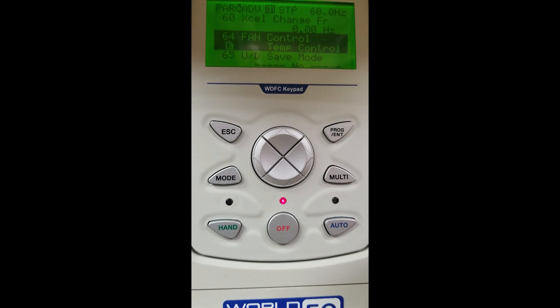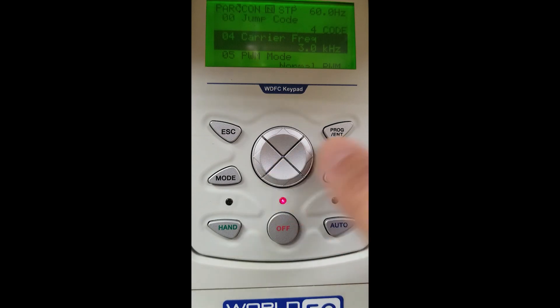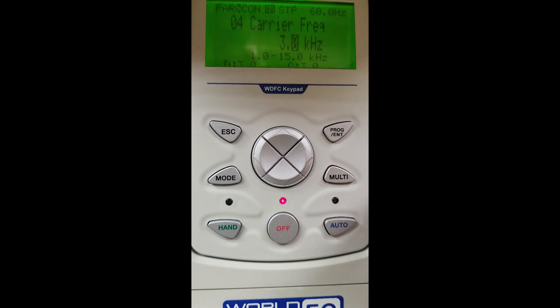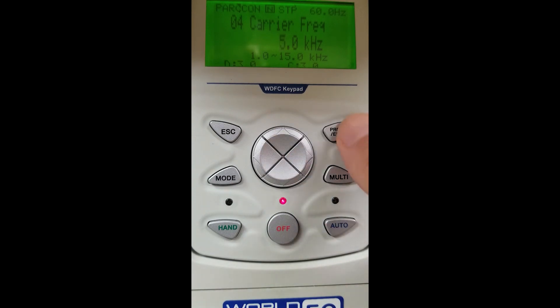Note the ADV label in the left-hand corner — this is how we access all our advanced parameters. If we hit our right arrow key, it goes to CON, which is our control group. Inside our control group, one very important parameter is our carrier frequency, which is CON04. Our carrier frequency in this VFD is set at 3 kilohertz. If you have any motor noise, you can enter that parameter and change it. We are going to change it to 5.0 kilohertz and hit our enter button to store that.